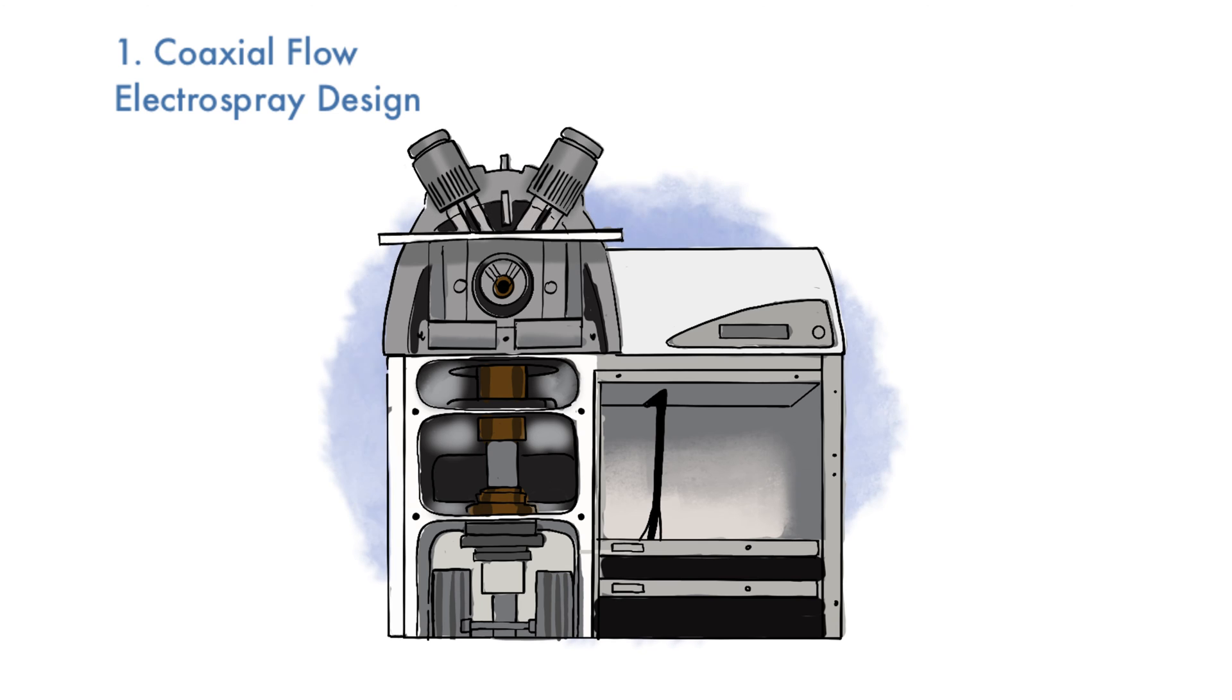The coaxial flow electrospray design prevents dispersion of like-charge species in front of the sampling orifice, which creates more effective ion sampling and leads to greater sensitivity. The coaxial flow electrospray is placed at 90 degrees to the sampling cone, effectively cleansing it with liquid eluent. This protects the sampling cone from contamination.